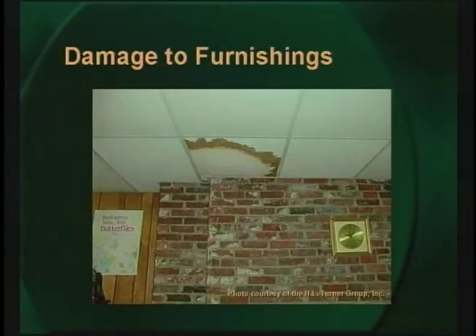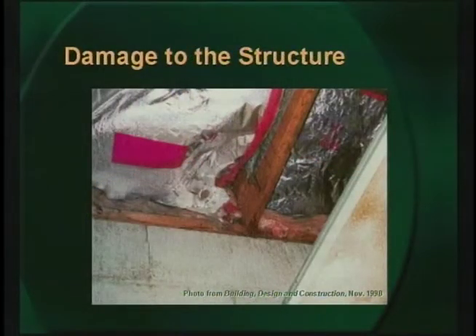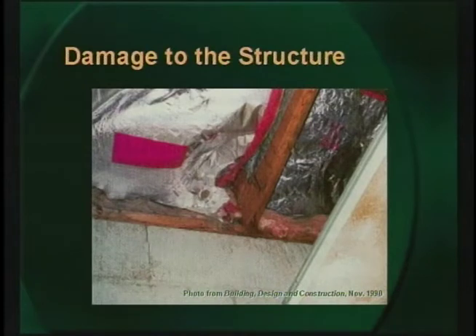In addition to the health issues, mold also prematurely deteriorates building furnishings and the structure. Common areas affected include the underside of wall coverings, ceiling tiles, and carpets. This photo shows a ceiling tile repeatedly exposed to moisture and as a result is now contaminated with fungi. It indicates a possible roof leak or an ongoing condensation problem above the ceiling, and the only remedy at this point is to replace the tile. Here's a photograph from another building with a history of condensation in the ceiling plenum area. Notice the discolored ceiling tile and the deteriorated wood framing. The condensation in this case was not the result of insufficient insulation, but rather the lack of a suitable vapor retarder on the warm side of the insulation and walls.